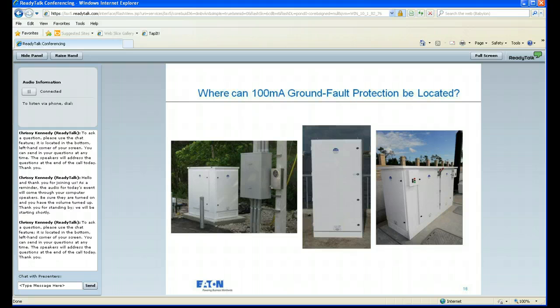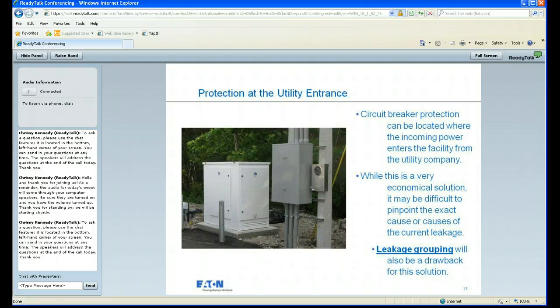Now we'll get into where you can actually locate this ground fault protection. There are a lot of different locations you can place it, and they all have pros and cons on not only cost, but also being able to detect what boat or boats are causing the leakage into the water. We'll start with protection at the utility entrance. You can put an enclosed circuit breaker with GFI protection. There are also a couple of other different methods, but that enclosed circuit breaker is the most popular.